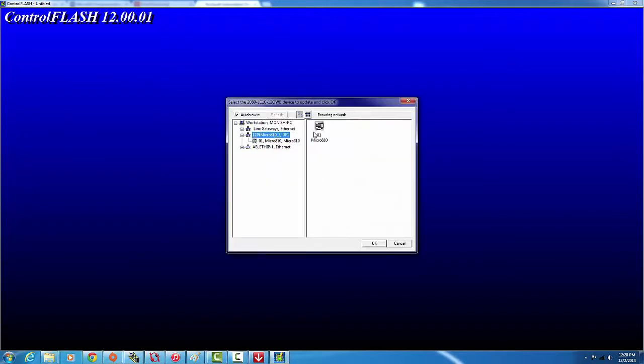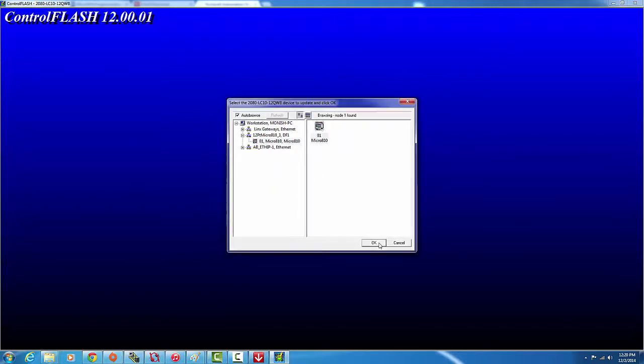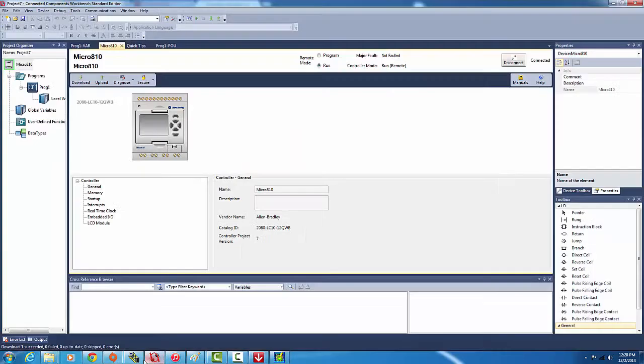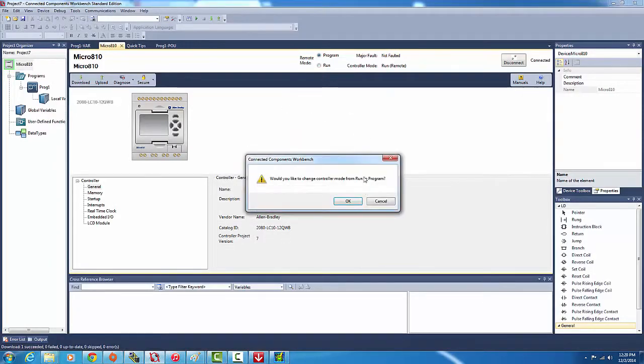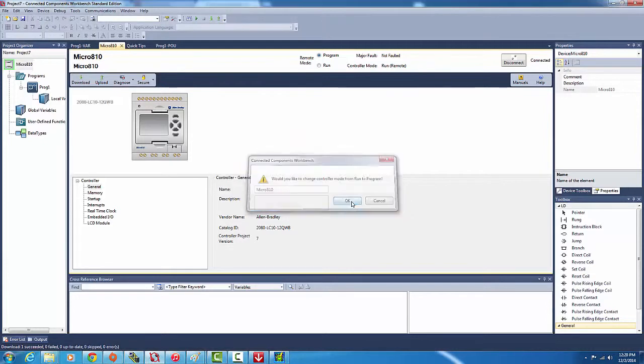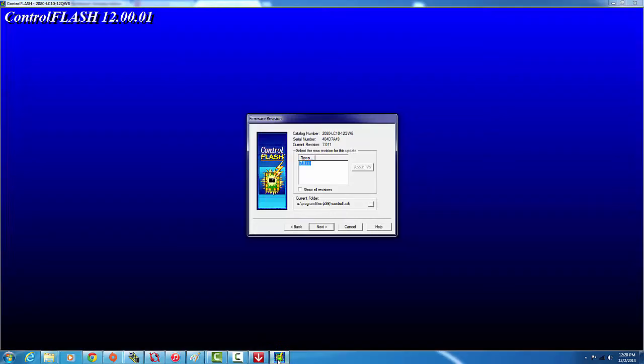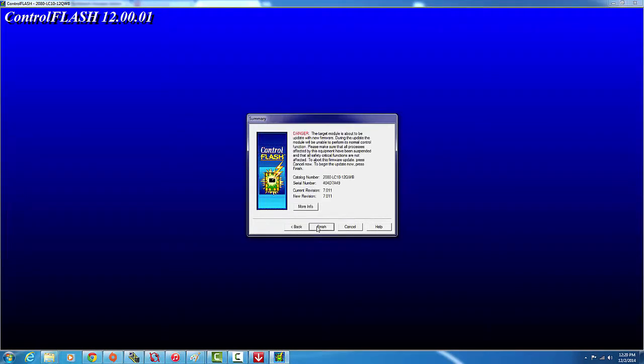Pick it from the list here. Just make sure it's connected and powered up. Pick the revision you want to install. This is the tricky part: you got to make sure your controller is on Program mode. If it's on Run mode, then the flash update will not work. Then we click Next, and we Finish. It updates, installs, and that's how the cookie crumbles.